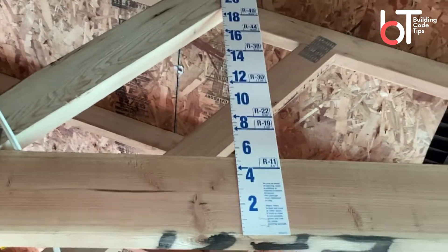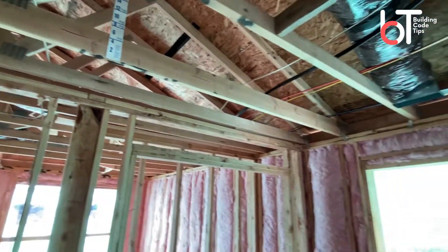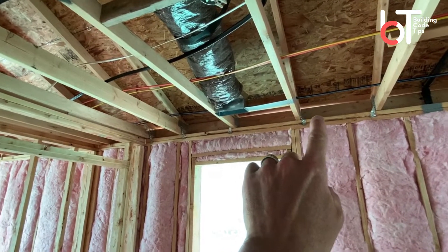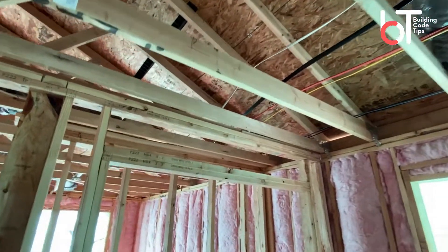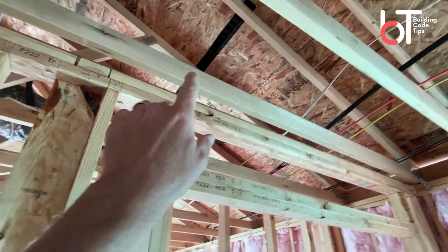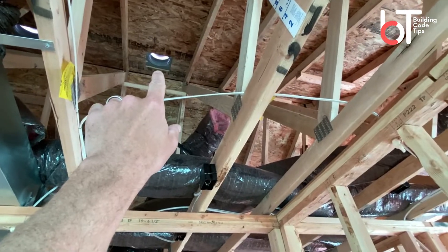The other thing to look for, which they've gotten away from in this particular house, would be soffit venting and baffles — the cardboard baffles. What they've done is gotten rid of the soffit venting and gone to what they call an inline intake vent that's just cut in and allows air to come in and go up and out through the can vent in the ridge.